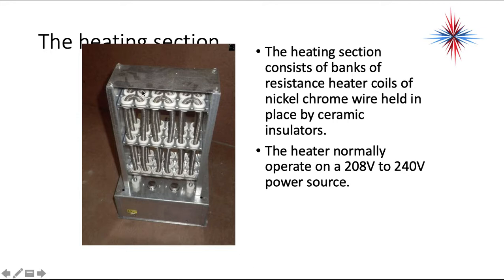If you look at this heat section in the picture here, you'll see the nickel chrome wires. These are the resistive elements that actually get hot. This is in the airstream, so all the air coming out of the blower blows through this before it goes into the ductwork. There are two safeties down here. These are our high limits. If for some reason airflow stops across this, the high limits will eventually open before there's a chance of fire.